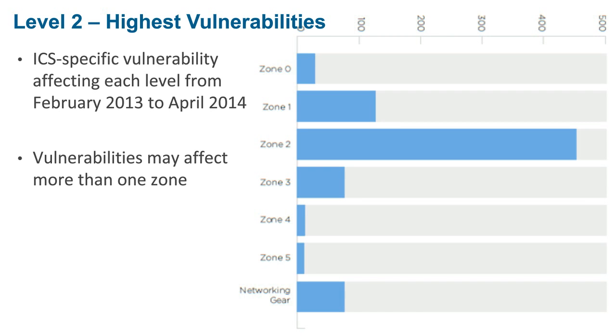Zone two — which tends to be standard systems around HMIs, operator workstations, and historians — is actually where you have the highest level of vulnerability in most environments. Not that we haven't seen vulnerabilities in programmable logic controllers, and from a safety and availability perspective we're particularly concerned about risks targeting physical systems. But often in an attack cycle there's a pivot point: someone starts at the easy-to-exploit Windows system or something more directly connected to the IT network, and uses that as a pivot point to then get into the physical systems.